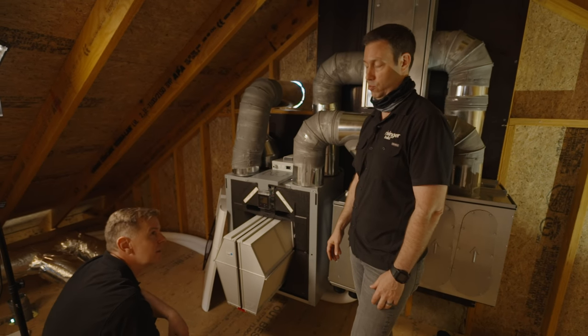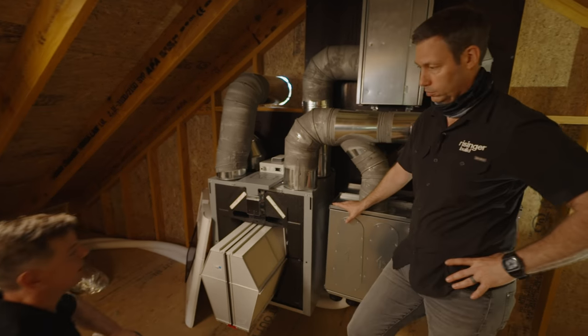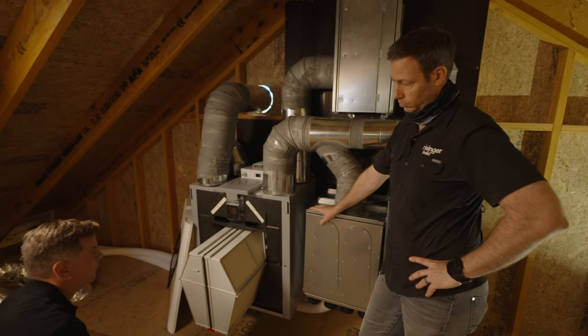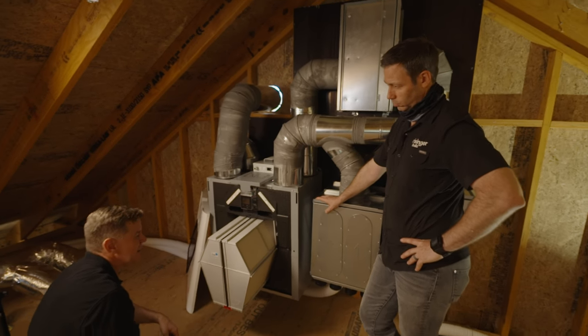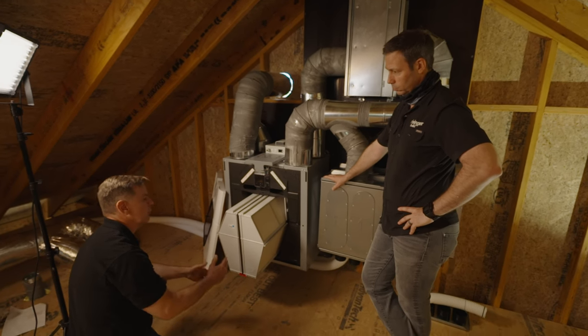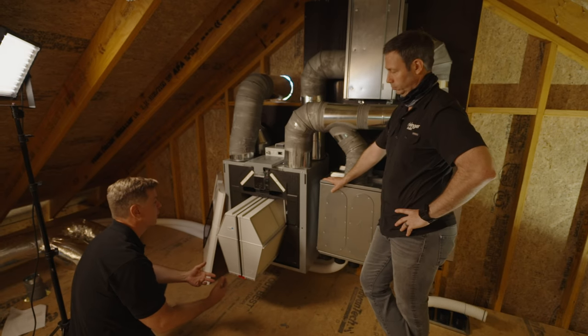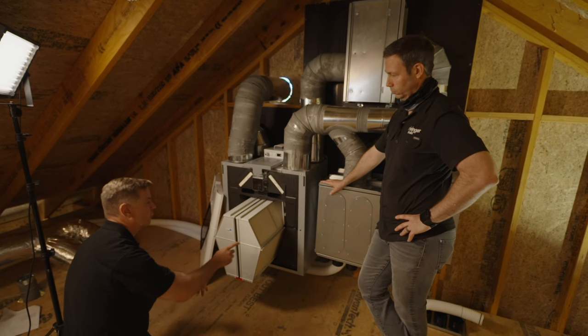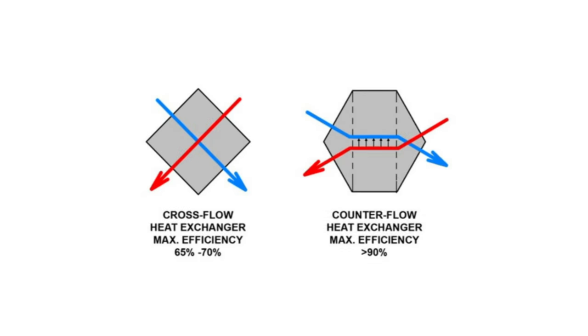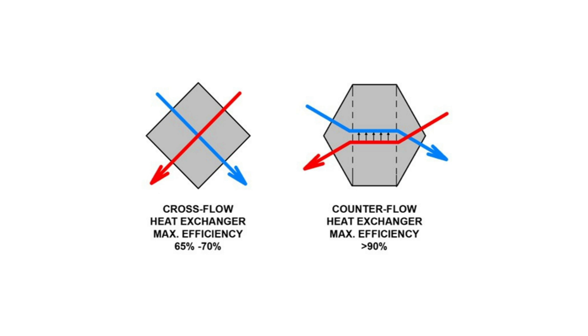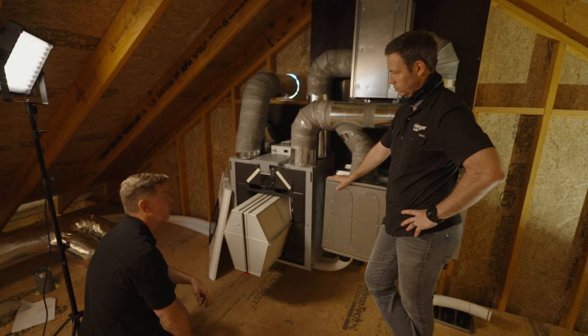That's crazy numbers. Yeah, what you'll usually see, very common especially in the North American market but now even in China, is the cross-flow heat exchanger. And you know it's cross-flow because it's just a square - the two air streams just go past each other like that, and each channel just has one point of contact. Here, when you see this hexagonal shape, that's when you know you're dealing with a counterflow heat exchanger, and you should just expect you're going to get much better performance.